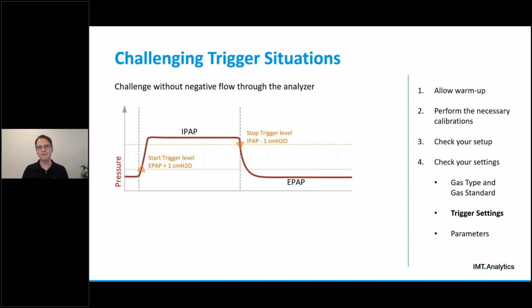In BiPAP ventilation, the upper pressure level is called IPAP and the lower pressure level is called EPAP. And in such a situation, we would typically set the start trigger level to EPAP plus 1 centimeter of water pressure on a rising edge and the stop trigger to IPAP minus 1 centimeter of water on a falling edge of the signal. And that ensures quite accurate triggering in this example. However, the challenge here is that the pressure levels are going to change when we change the settings on our ventilator. So let us have a look at that in a real life situation.